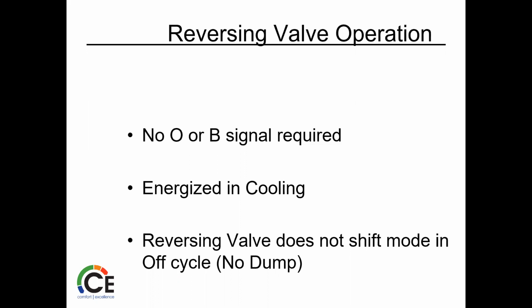The reversing valve does not shift mode in the off cycle. So if we're in heating, it stays in heating until it gets a cooling call. So you won't see it equalize. That's a big difference with commercial units.